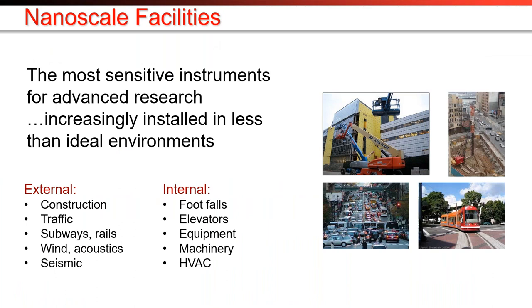Increasingly, new advanced research facilities are being sited in urban environments — environments that are hostile from a floor vibration perspective. Floor vibration comes from two directions: either from inside the building or from outside. Externally, you have things like construction, road traffic, trucks, cars, subways, light rails, and trains. Also wind and acoustics — wind driving on a building will excite resonant structures and increase floor vibration.